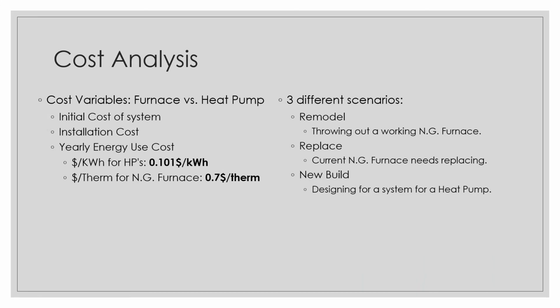Using bin weather data, along with efficiency factors from air source heat pump and natural gas furnace spec sheets, we will be able to create a cost analysis model to compare yearly energy cost. Once we have created this model, we will compare overall cost for 3 different scenarios. The first scenario is a remodel, in which a working natural gas furnace will be thrown out and replaced. The second scenario is a replace, in which the current natural gas furnace already needs to be swapped out. The third scenario is a new build for a system that is designed specifically for an air source heat pump.